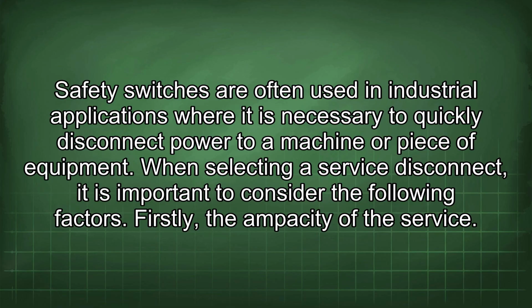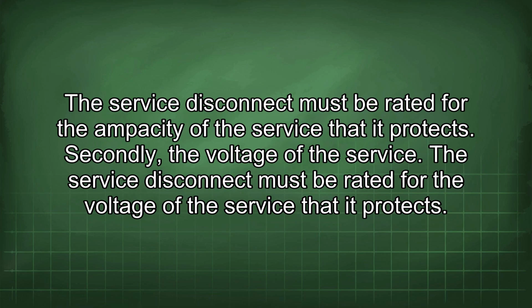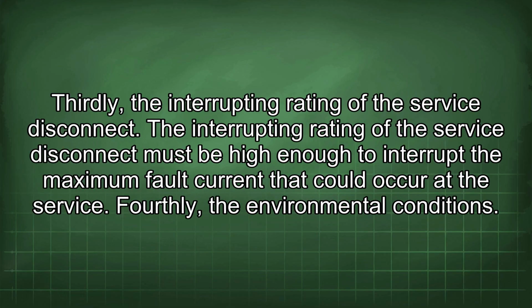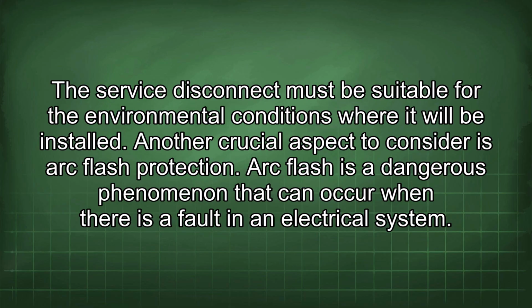When selecting a service disconnect, it is important to consider the following factors. Firstly, the ampacity of the service. The service disconnect must be rated for the ampacity of the service that it protects. Secondly, the voltage of the service. The service disconnect must be rated for the voltage of the service that it protects. Thirdly, the interrupting rating of the service disconnect. The interrupting rating must be high enough to interrupt the maximum fault current that could occur at the service. Fourthly, the environmental conditions. The service disconnect must be suitable for the environmental conditions where it will be installed.